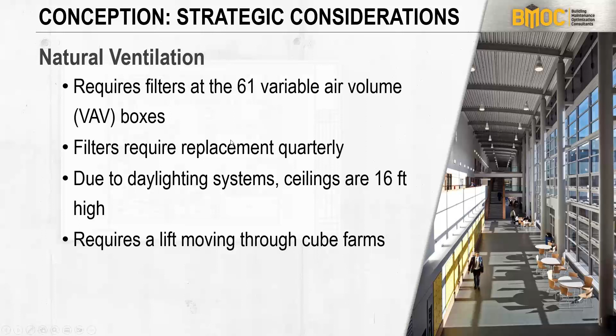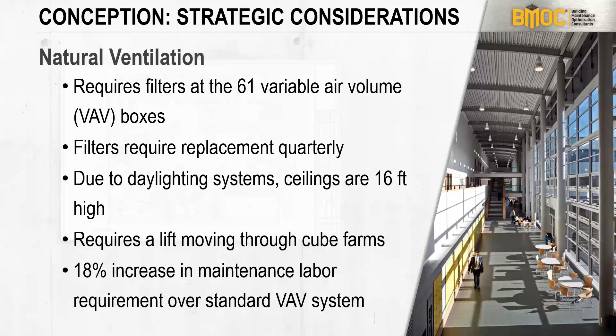Due to daylighting systems in this building, the ceilings are 16 feet high. That's to the bottom of the drop ceiling structure. And you needed a lift or a large A-frame ladder, even a 14-foot A-frame ladder. It takes up a lot of space when you're setting it up, but it required a lift moving through these cube farms. As another part of the daylighting, you had these low cube farms around the offices, and it was a beautiful building. But when you're replacing these filters quarterly, it's quite disruptive to the working environment. So we estimated that it represented an 18% increase in the maintenance labor requirement for the whole building over a standard VAV system.